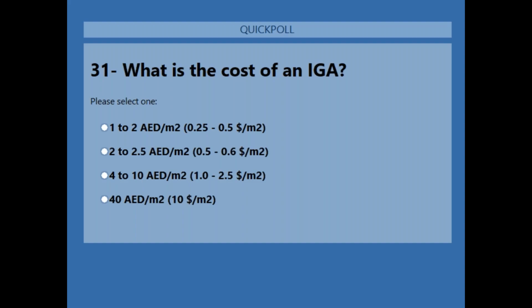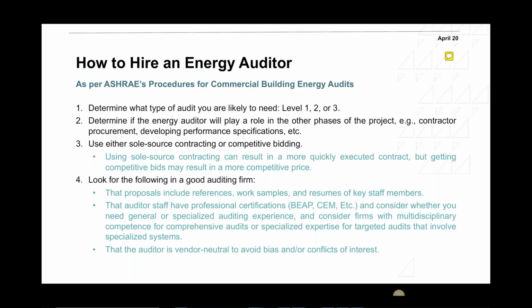The majority got it right, or this is what I think normally and what I've seen. A proper investment grade audit will cost you around 4 to 10 dirham per square meter, or in the US, maybe $4 to $10 per square meter. There's a good publication from the DOE, Department of Energy in the US, that shows the typical cost, which depends on the complexity of the project, not just the size. So there are two things: the breadth of the audit and the complexity of the building.